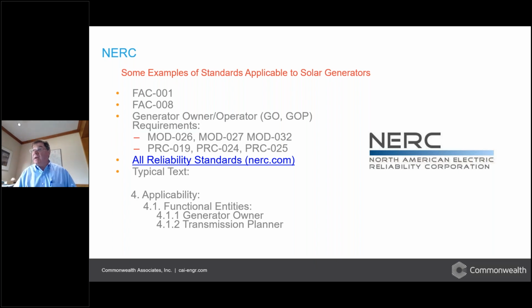That is a standard that every transmission owner must have that describes their interconnection processes. And it's an interesting one to look at because it may not always be entirely consistent with the practices that are going on. So if you really want to be expert, you go into that and interpret it and read it. FAC-008, as a generator operator, you have to file your circuit ratings. Those start to become a part of data that is created initially in the design phase.